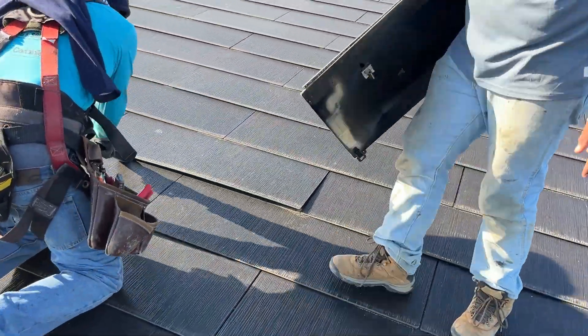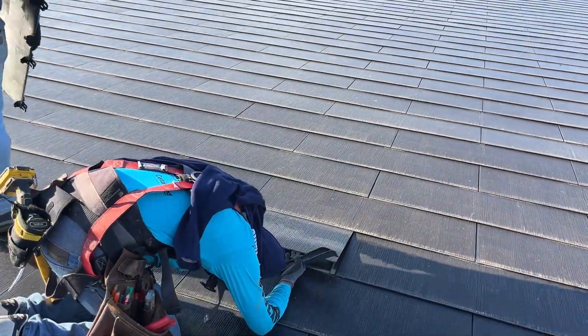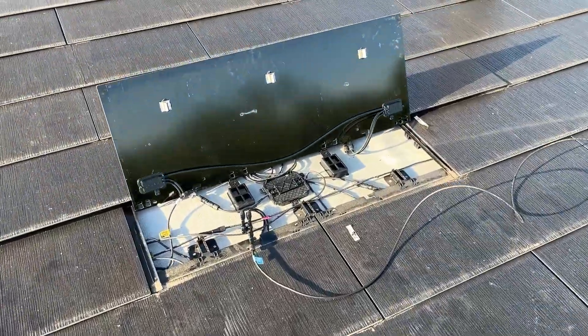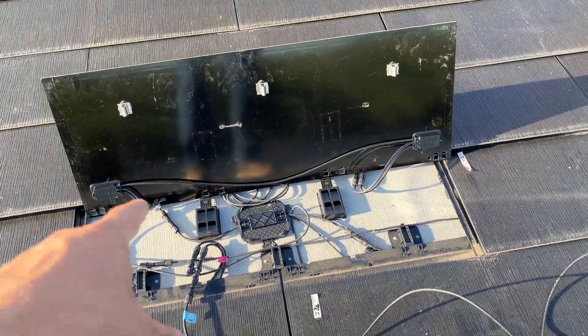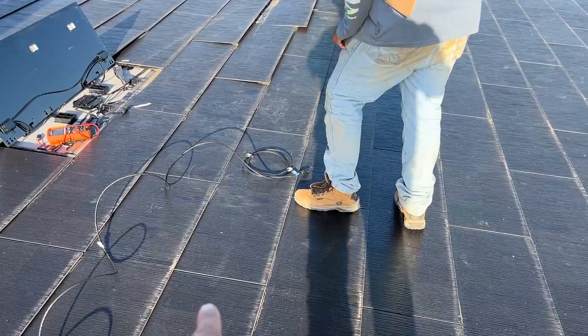The good news is look how easy it is to troubleshoot. So we were able to just pop these up. This is where it all comes through. We're able to measure the strings and we know exactly where the potential problems might be. And then you just flip this up. You pop it up and you flip it up just like the hood of your car. And you're able to test here. You see that they're moving over here — they're seeing if it's this string here.